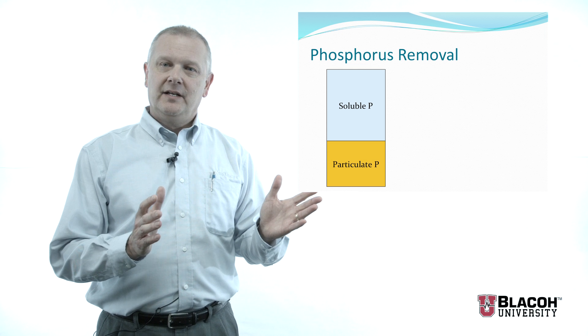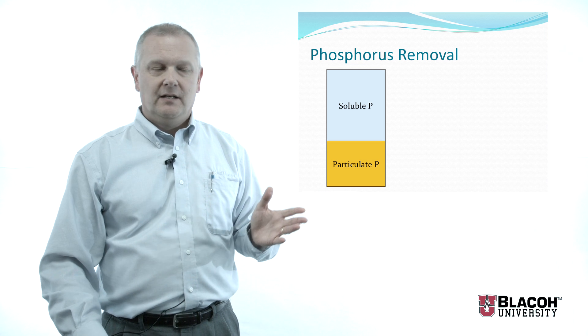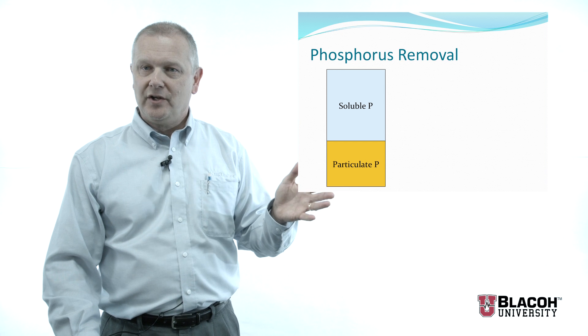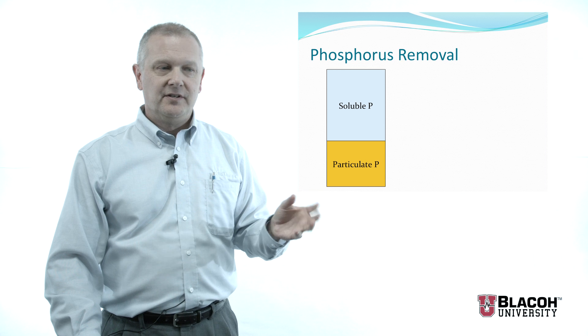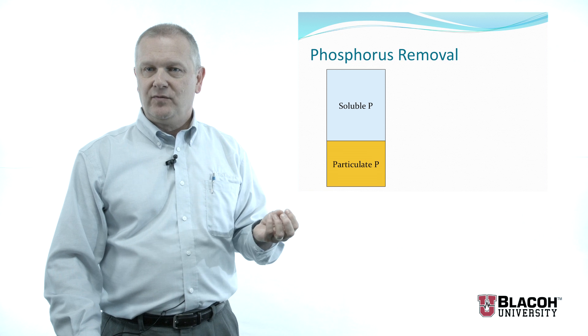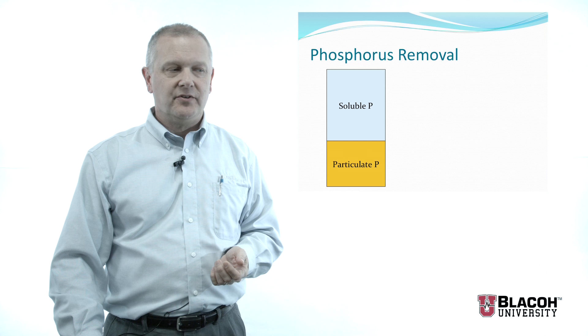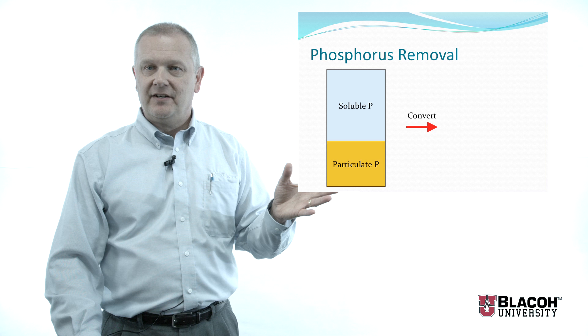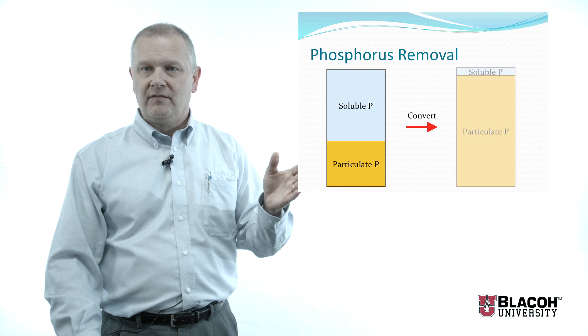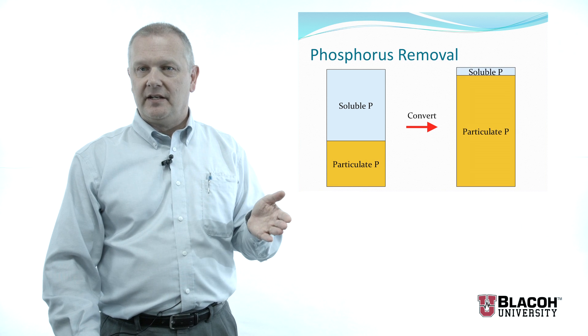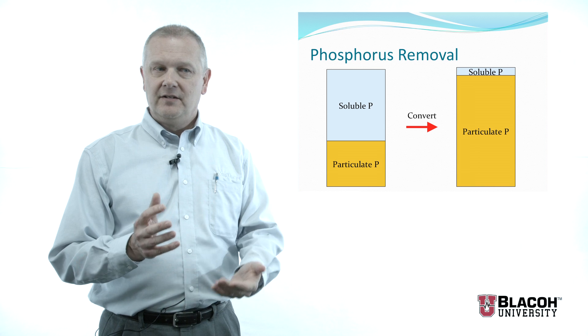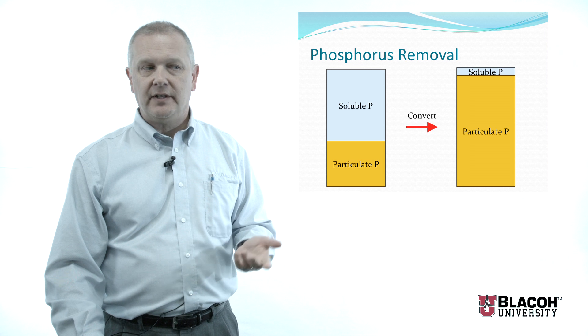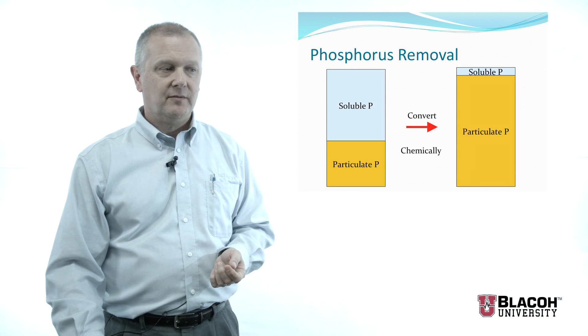Phosphorus removal can be summed up in this diagram. Phosphorus that comes into the treatment plant is about two-thirds soluble or dissolved and about a third in particulate form contained in organic molecules. The whole idea of phosphorus removal is to convert this scenario to one where almost all the phosphorus is particulate, so that it can be settled or filtered out of the water. We can do this two ways: chemically and biologically.